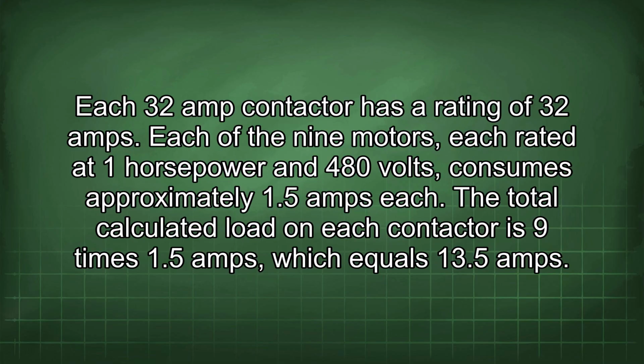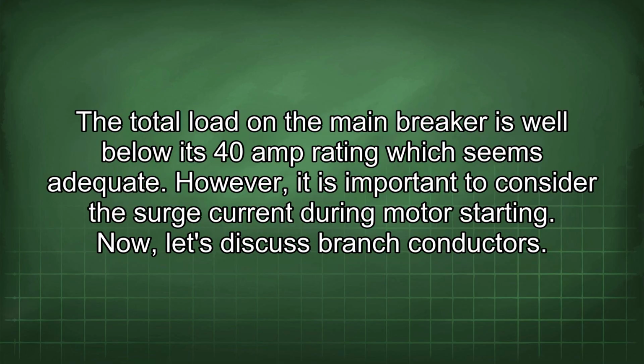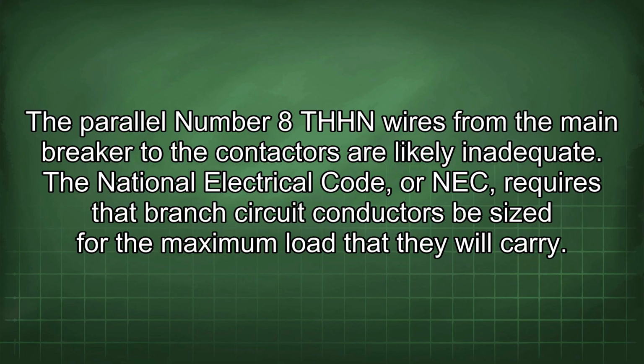The total calculated load on each contactor is 9 times 1.5 amps, which equals 13.5 amps. The total load on the main breaker is well below its 40 amp rating, which seems adequate. However, it is important to consider the surge current during motor starting. Now, let's discuss branch conductors. The parallel number 8 THHN wires from the main breaker to the contactors are likely inadequate.